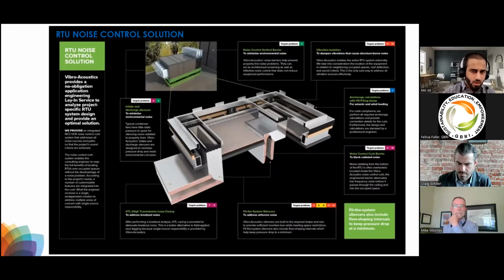We recommend, when selecting a rooftop unit, to have a noise control curb, which can reduce noise underneath the roof within the occupied space. Within a noise control curb, you would have a silencer and panels where the noise could be suppressed, and you would avoid duct breakout and transmission loss.